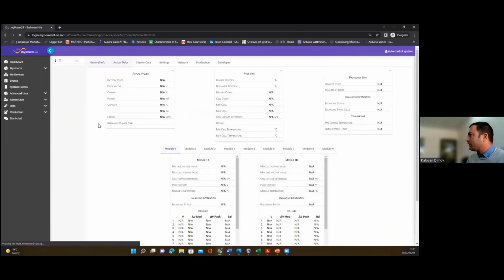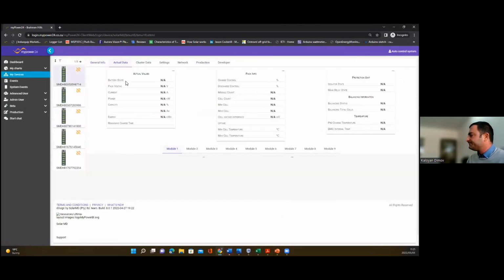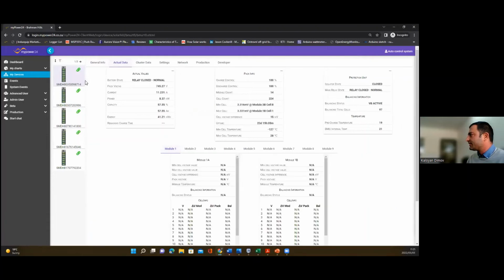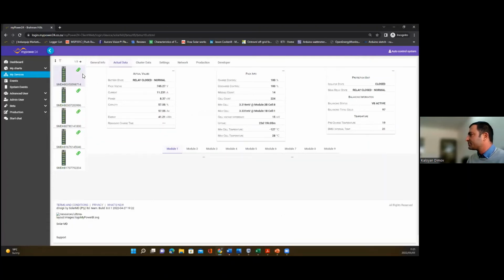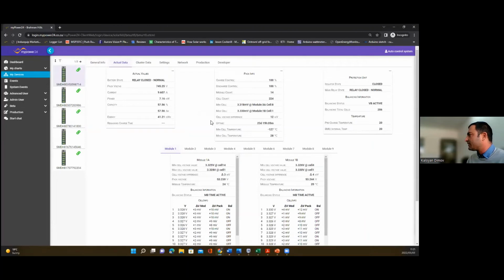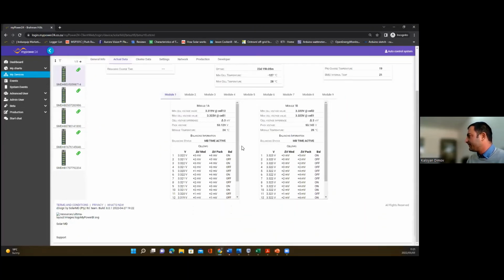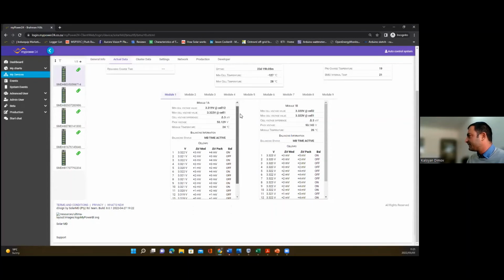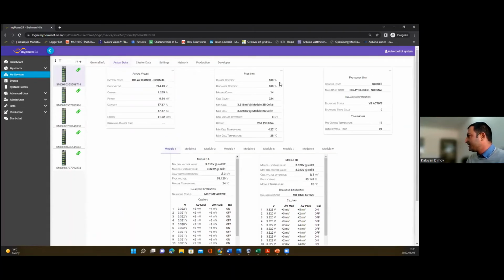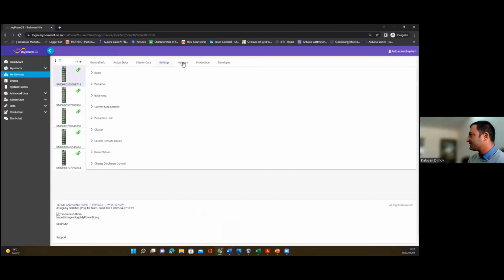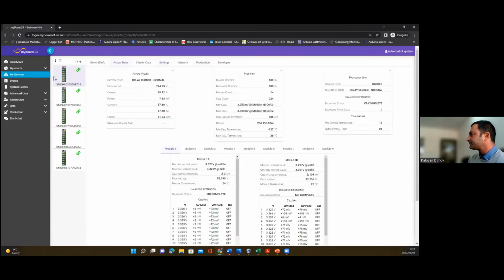We have our 12 high voltage battery modules connected in parallel. Each module, in this case, is 71 kilowatt hours. You can see all the information, drag down to cell level and temperatures of each module - the battery consists of 224 cells. Very detailed information: cell voltage differences, and multiple settings can be done remotely here.